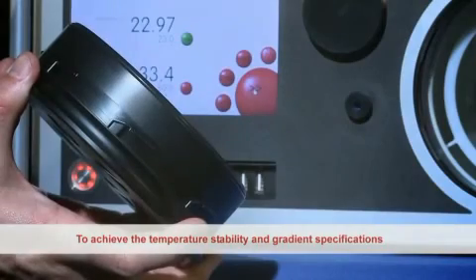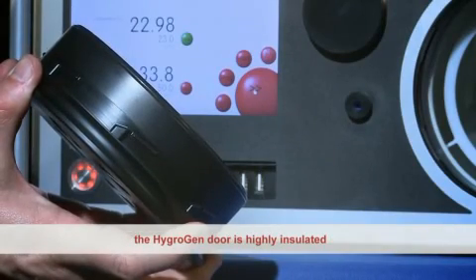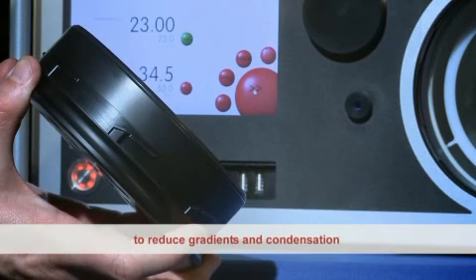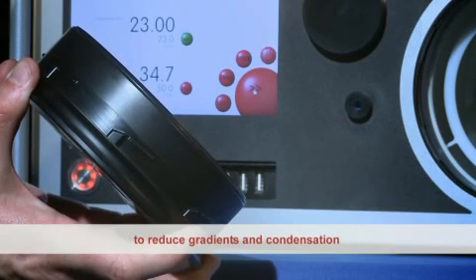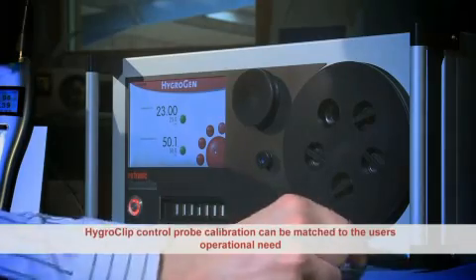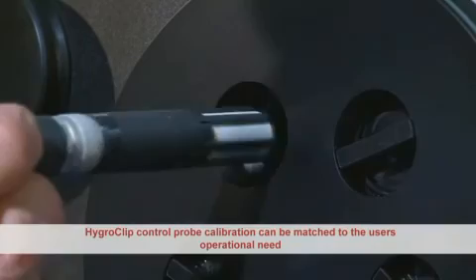To achieve temperature stability and gradient specifications, the HygroGen door is highly insulated and includes peripheral temperature control to reduce temperature gradients and condensation when running at high temperature conditions. The HygroClip control probe can be calibrated exactly to match the user's operational need.